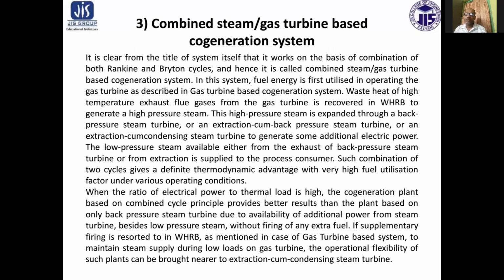Number 3, combined steam gas turbine based cogeneration system. It is clear from the title that the system works on the basis of a combination of both Rankine and Brayton cycles, and hence it is called a combined steam gas turbine based cogeneration system. In this system, fuel energy is first utilized in operating the gas turbine as described in gas turbine based cogeneration system.